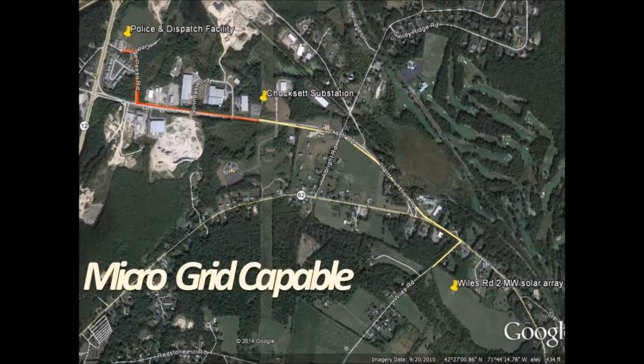We actually utilized it for this purpose, and as I speak we're in the middle of testing it, feeding the dispatch center live from the batteries right now. We've taken it off the circuit, opened the main recloser, and put it onto batteries, it's happening as I speak. To the right of that, you see the yellow line going back to our Wiles Road 2 megawatt solar array.